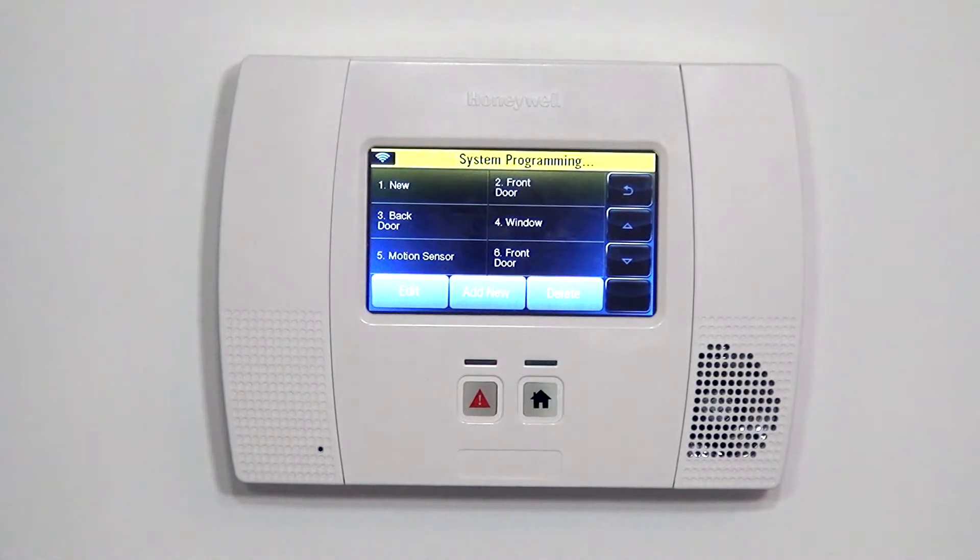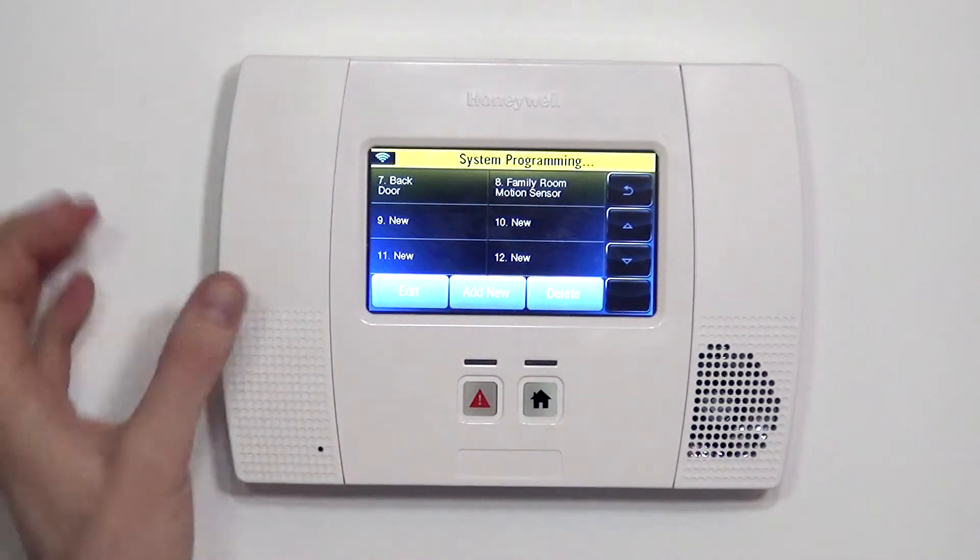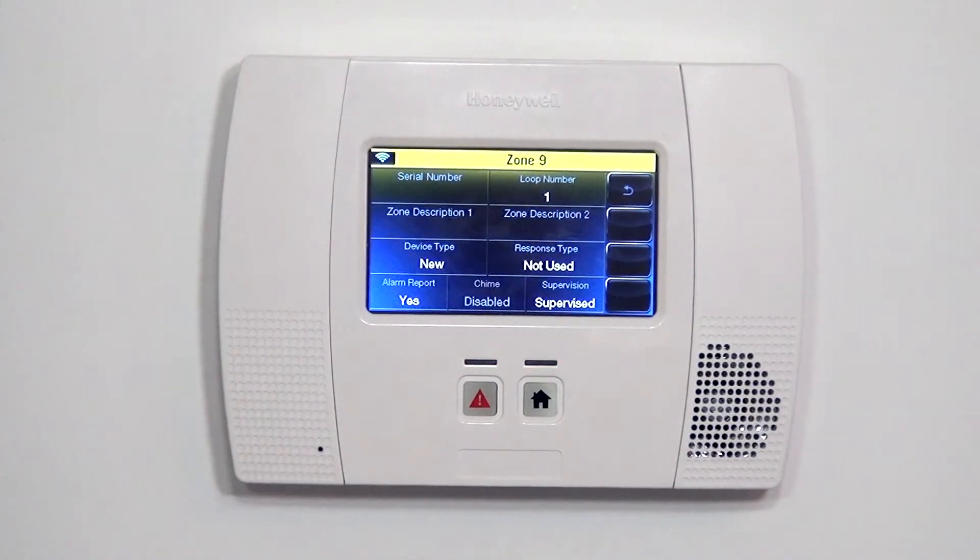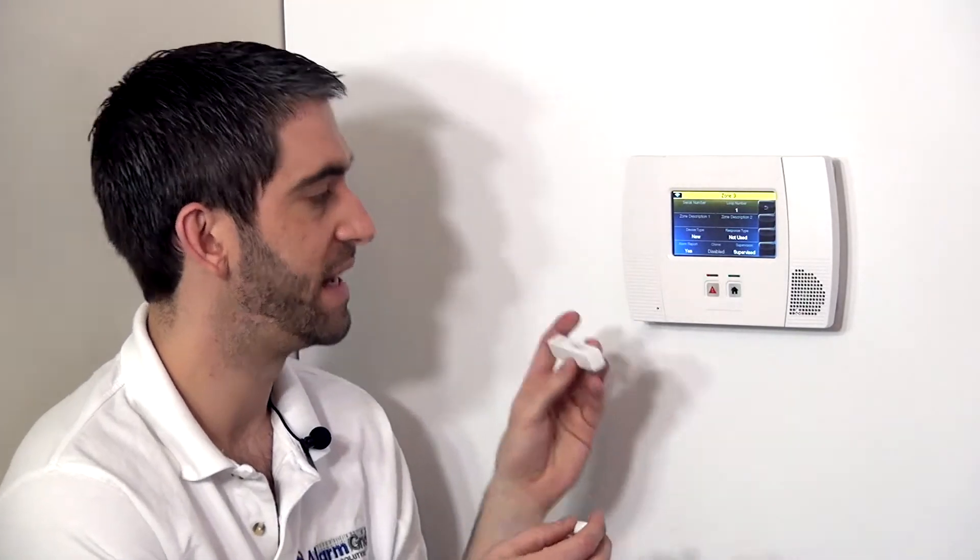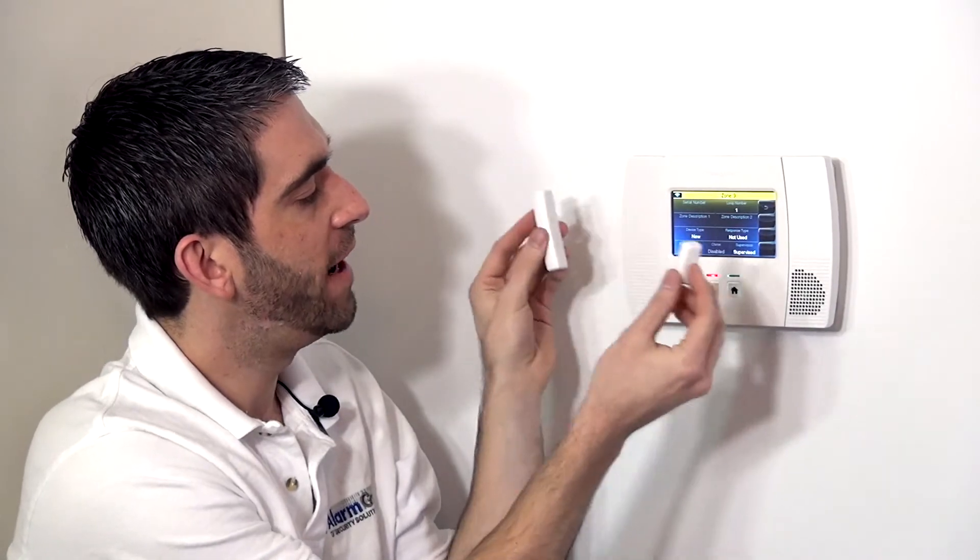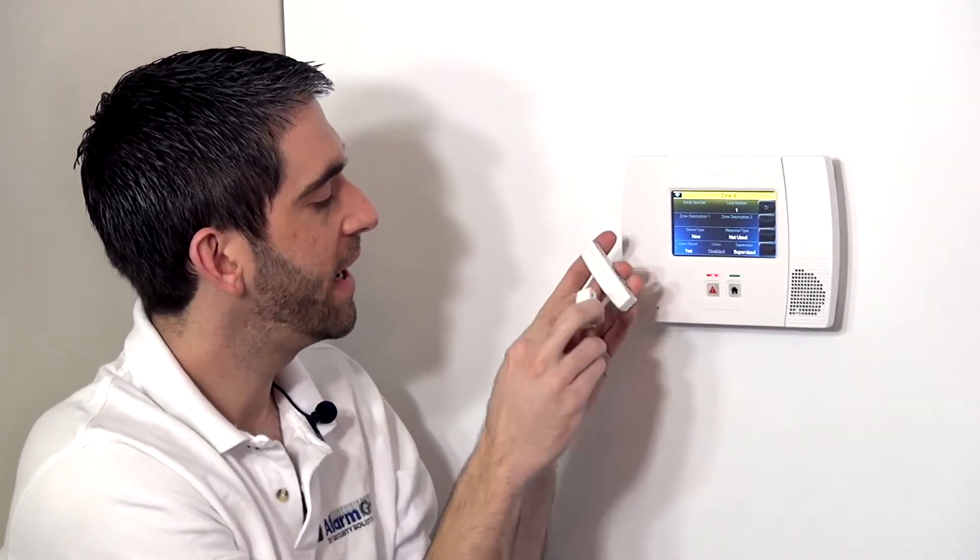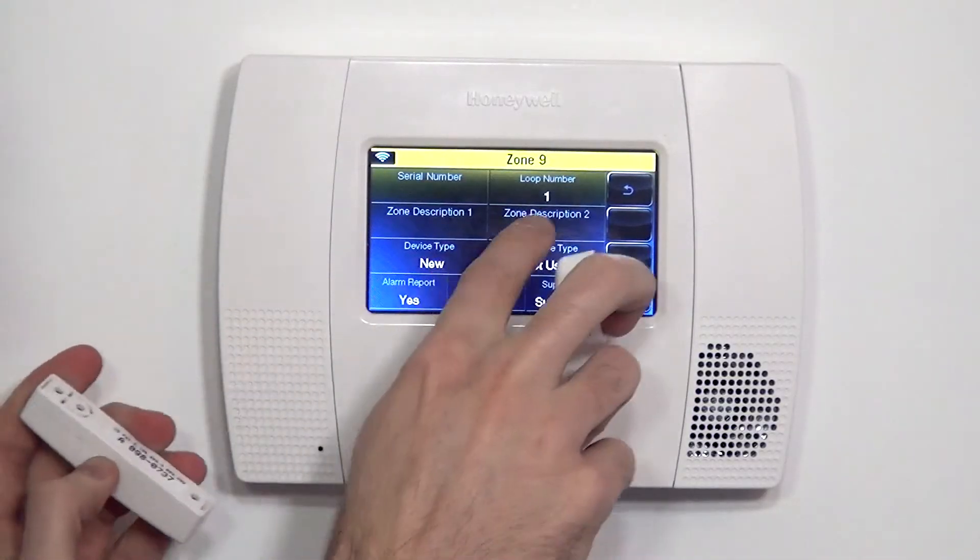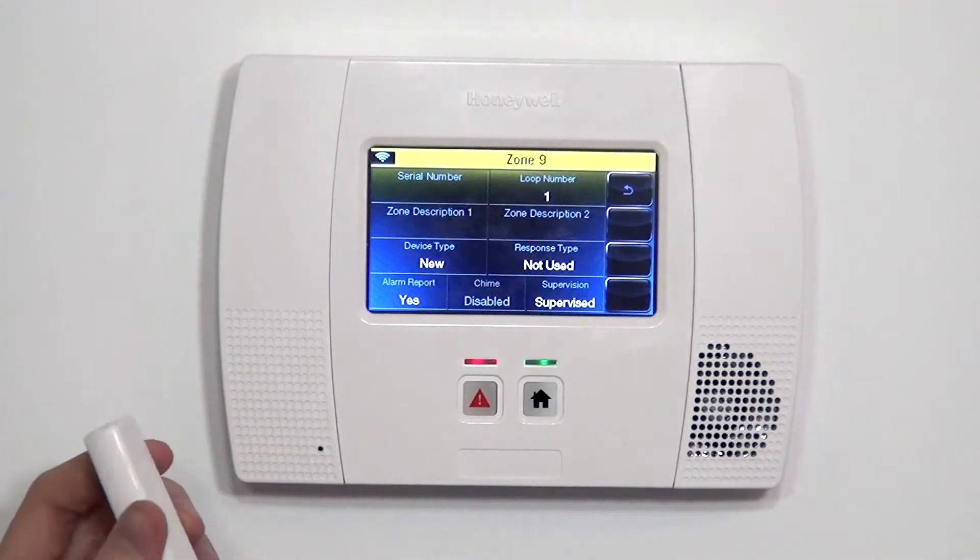If we go to Zones, that's where we use the screen to select the next available zone. We go to Zone 9 and click Edit, and now we can input this device to the system. To learn in any Honeywell sensor to the system, you need the serial number, or you can auto-enroll the device. We'd like to verify the sensor works and make sure that the proper serial number and the proper loop number get learned in.